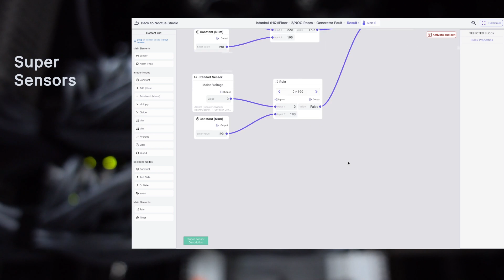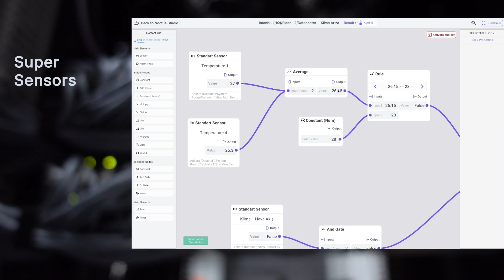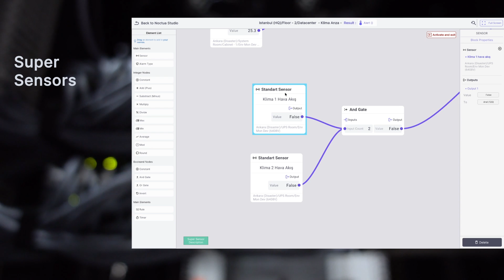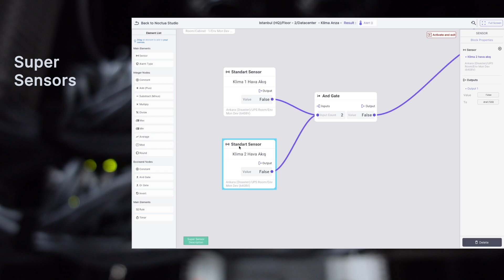Can you give an example? Let's say you want to detect a refrigeration fault. You could create a super sensor that only triggers an alarm if the room temperature goes above 28 degrees Celsius and a separate airflow sensor confirms the AC unit's fan is actually running. If the temp is high but the fan is off, maybe the unit just lost power. But if the fan is running and it's still getting hot, that points more specifically to a cooling mechanism failure.